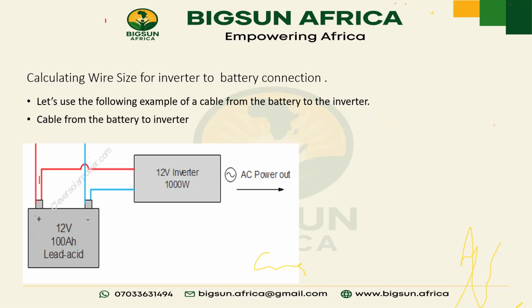In this case, if we are going to get our VDI, VDI is going to be what? The current. We are not looking at the panel now, we're looking at the battery. So it's going to be the battery current, which is 400, right? Yes, sir. Times what? We are going to times this 400 by the safety factor first, which is 1.3. So what's 400 times 1.3 going to give us?